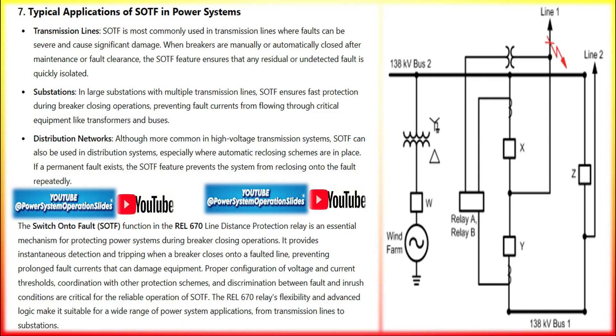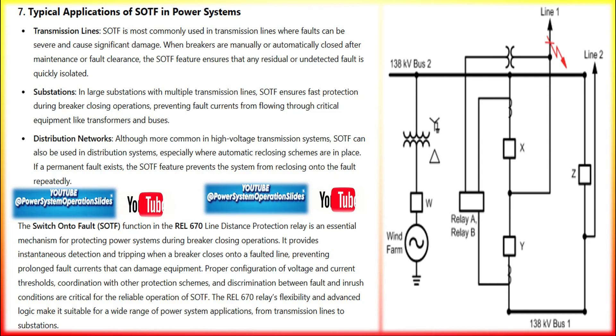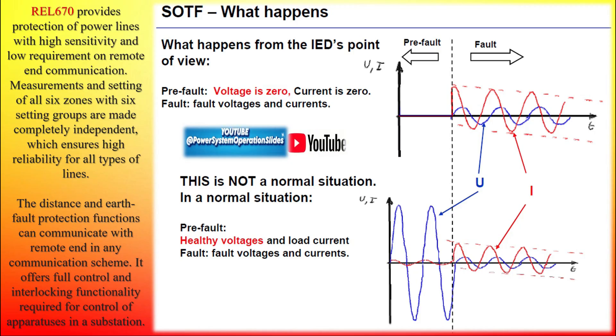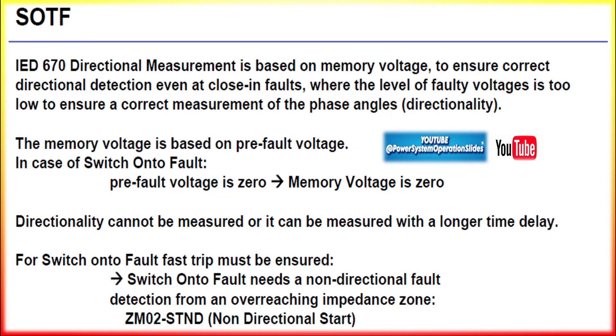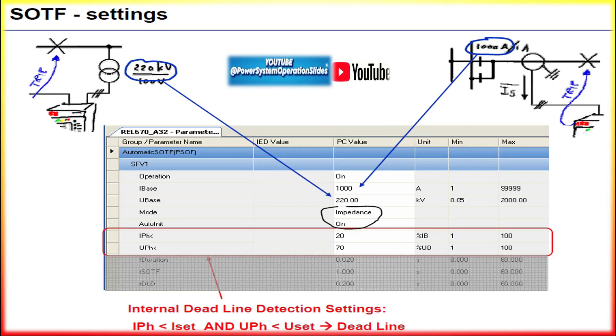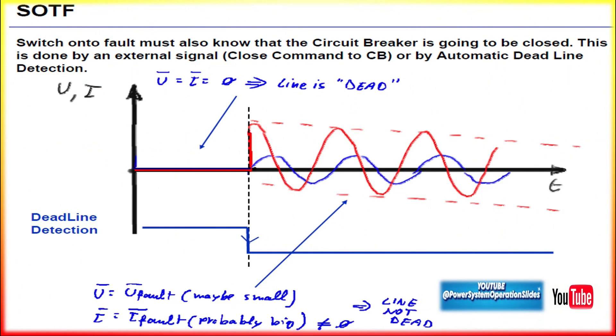The typical sequence for SOTF operation in the REL670 is as follows. First, monitoring the line voltage: the relay continuously monitors the line voltage. Before the breaker is closed, the voltage is near zero if the line is de-energized; if there is a fault, this voltage remains very low. Second, breaker closure detection: the relay detects when the circuit breaker is about to be closed using breaker status contacts or auxiliary contacts, and prepares for potential fault detection. Third, fault current detection: once the breaker closes, the relay looks for a sudden spike in current. If the current exceeds a preset threshold — much higher than normal load current — it assumes the breaker has closed onto a fault. Finally, instantaneous tripping: the SOTF function bypasses normal protection settings like time delays or zone coordination and sends an immediate trip signal to isolate the faulted line.